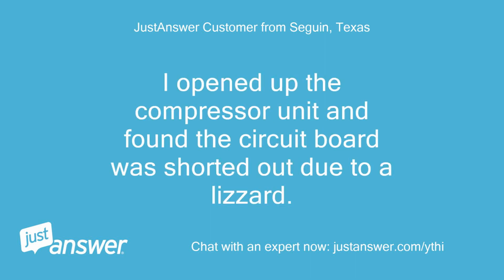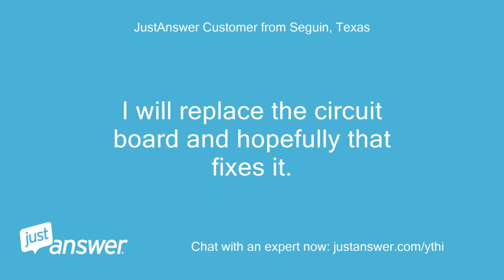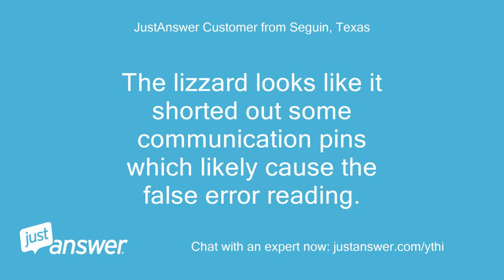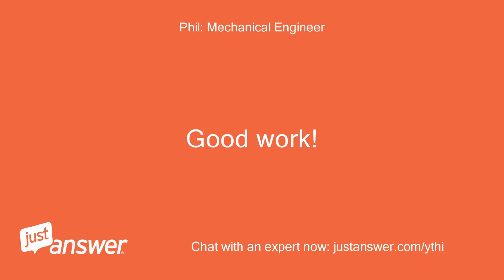I opened up the compressor unit and found the circuit board was shorted out due to a lizard. I will replace the circuit board and hopefully that fixes it. Thank you for pointing me toward the compressor and away from the plasma error. The lizard looks like it shorted out some communication pins, which likely caused the false error reading. Good work.